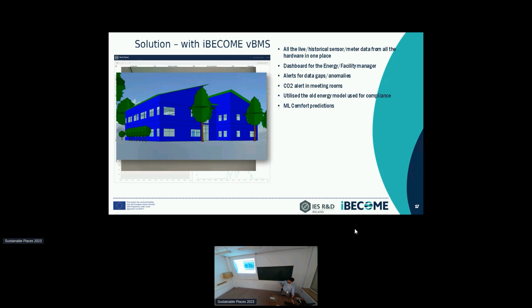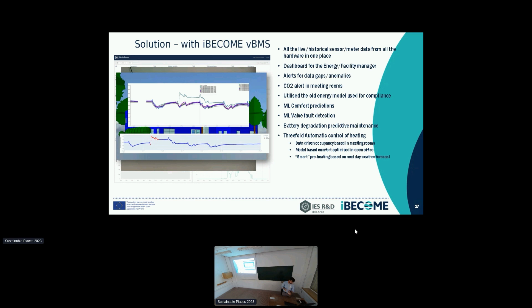We used this model again, updating and calibrating it to make predictions and create scenarios. We trained algorithms on the model's results to perform comfort predictions, fault detection, and battery degradation analysis - predictive maintenance to replace sensor batteries before they go offline. This also enabled data-driven, occupancy-based heating control in meeting rooms, comfort optimization in open office areas, smarter preheating of the building, and a demand response advisor using external data like energy price or carbon intensity forecasts. We advise building occupants to, for example, charge devices an hour later when energy is cheaper, demand is lower, or grid carbon intensity is lower.